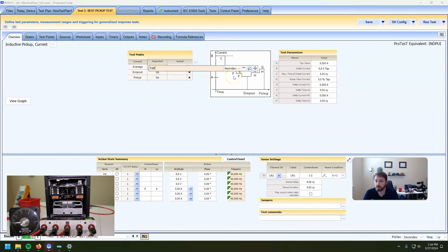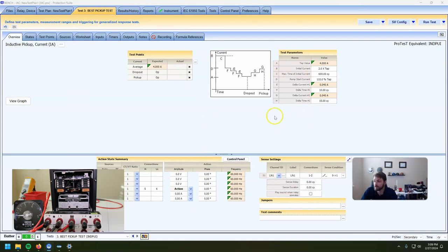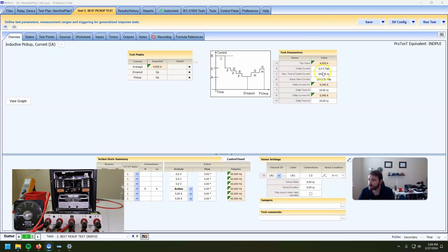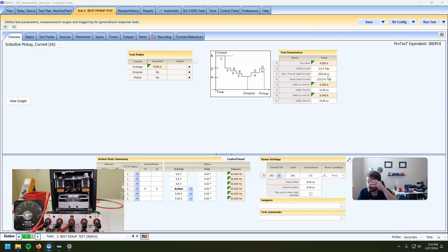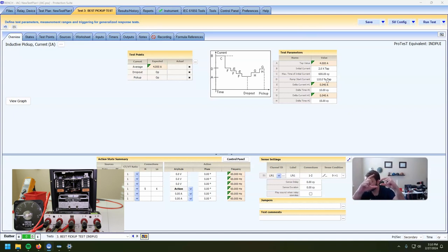Our average here is tap — that's what we want our expected value to be, four amps. Our target is the actual pickup value, four amps. Our initial current: we're going to start way above the tap to give the time over current unit time to physically close all the way, for about five seconds. Our ramp start current — our tolerance is plus minus five percent, so our test needs to start above that. We ramp down until we're in the tolerance, at which point it should drop out and the induction unit trip contact should open. We're going to watch it open and then immediately turn back around and start ramping back up.